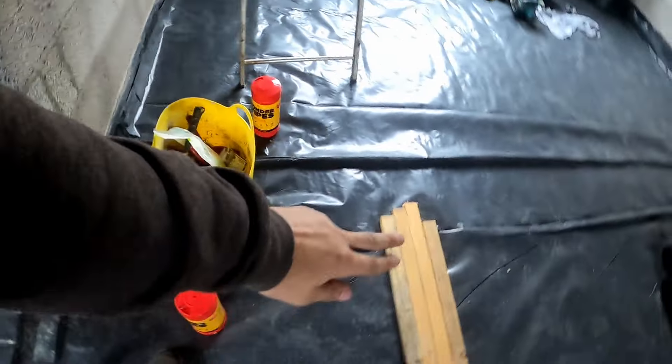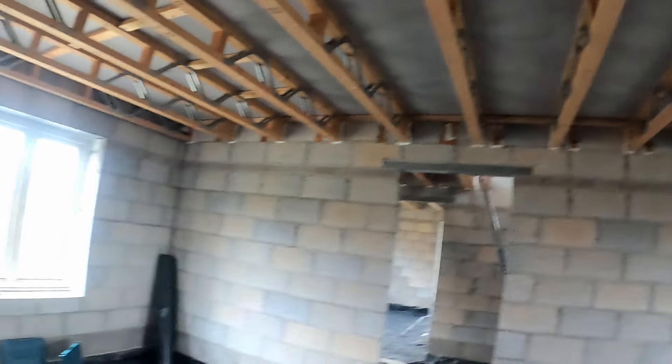I've been around and dropped all my soil pipes in up to first floor height - that's as far as I'm going to take them until I get the proper layout. I'm thinking about my hot, cold, and flow and return coming from this point across to my airing cupboard. I've picked up a load of Pantowl which we can run across, get all our clips on, and then just lift the pipes up. Down here we need a hot and cold into the cloakroom. I might run a balanced cold off the manifold block for my bathrooms. Showers and baths are a bit more sensitive to uneven pressure, so I might just run a cold off my multi-block from the cylinder back to these two bathrooms. Rather than running the cold across - if we've got four bar coming in and then three bar, you can have slightly uneven pressures on your showers. Just for the sake of a little bit of extra pipe, I'll just run it back to there.